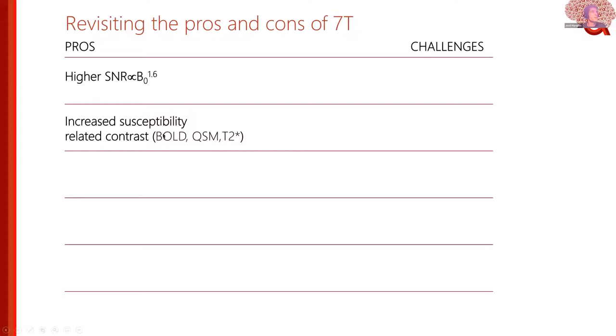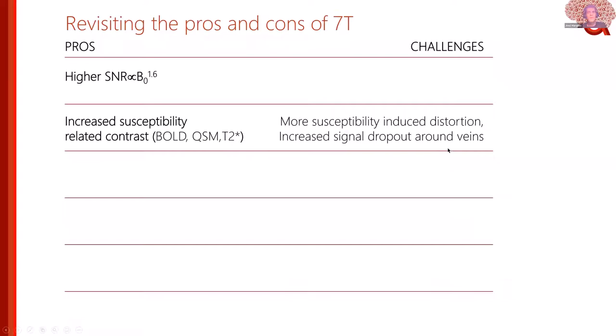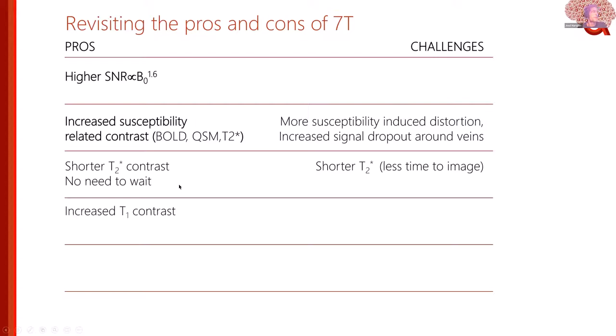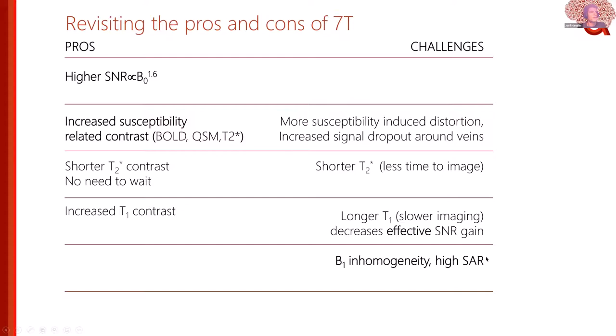To summarize the pros and cons: you do get high SNR that allows great images, and increased susceptibility contrast, which is good for T2-star contrast but also causes more geometric distortion with EPI readouts and signal dropout near air-tissue interfaces. Veins tend to dominate some images. Shorter T2* means less time to acquire. Increased T1 means slower imaging, reducing the effective SNR gain. And there is significantly higher SAR — you tend to deposit a lot of energy in subjects.